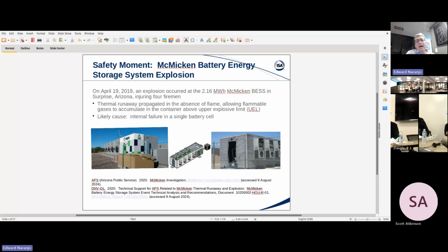As it turns out, one of the cells in this particular container had a runaway reaction, and it propagated to the point where the accumulated hydrocarbon gas was above its upper explosive limit, and as a result it could not sustain a fire. Yet an alarm was raised, and a number of firemen went to investigate the incident.